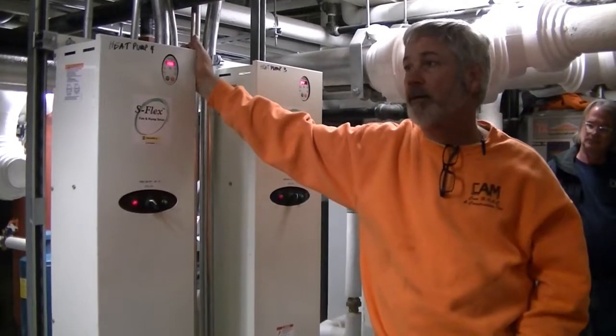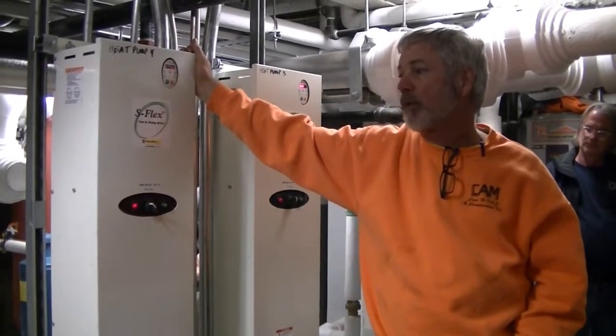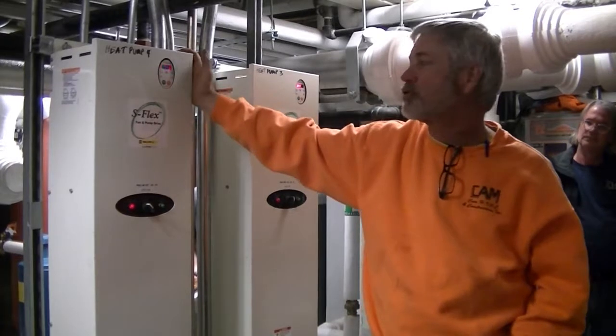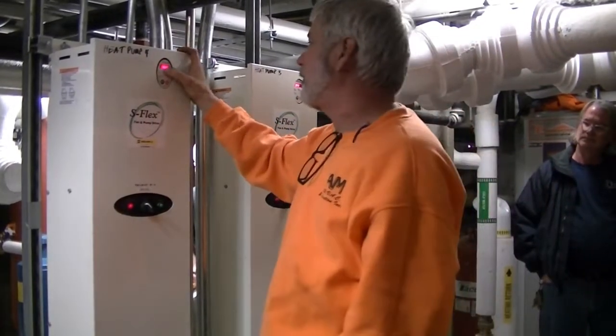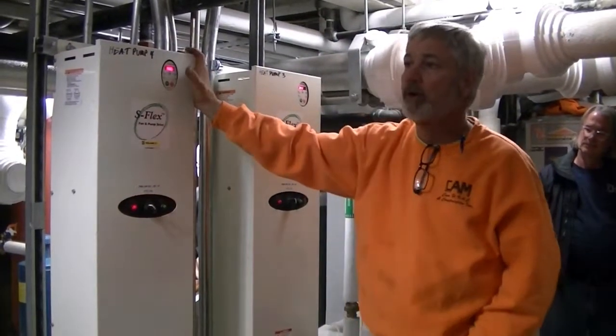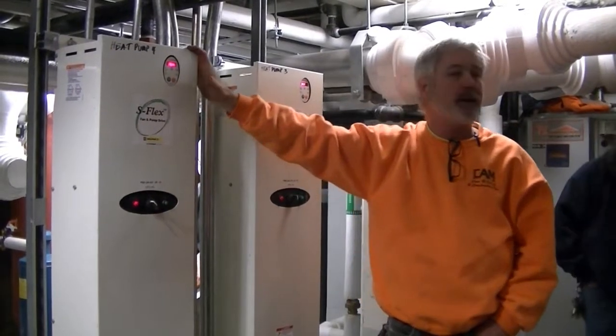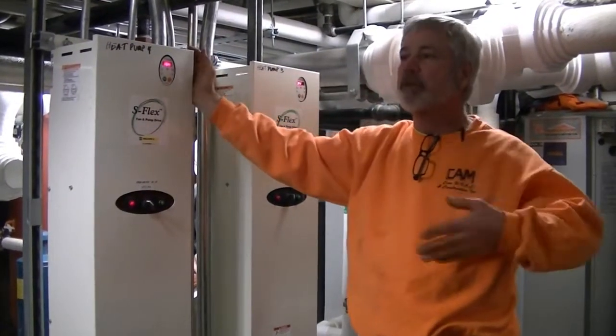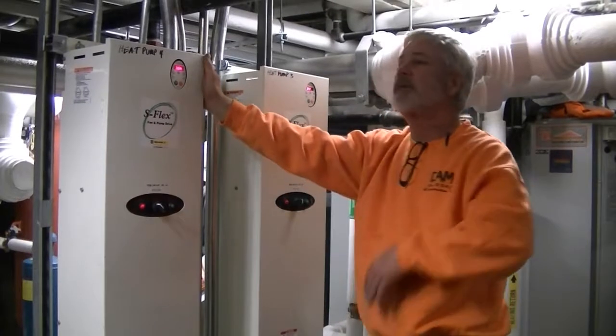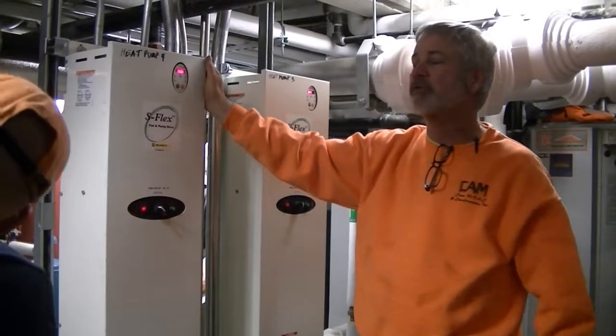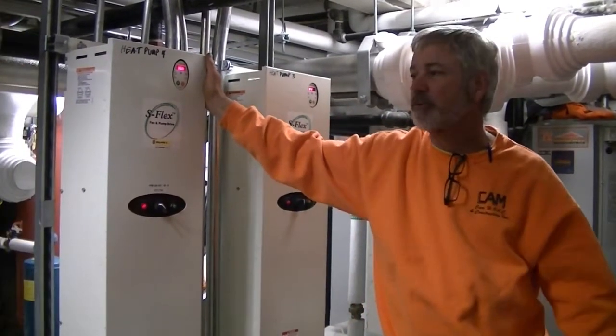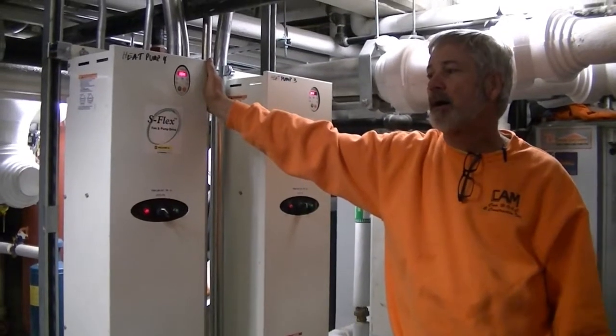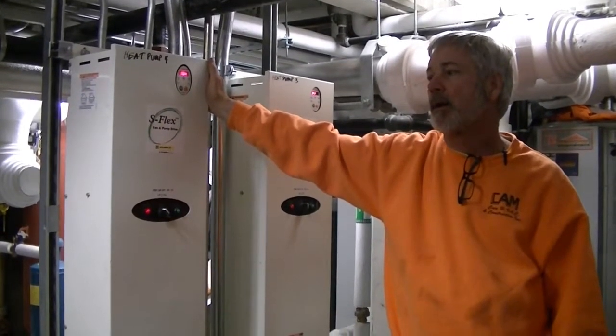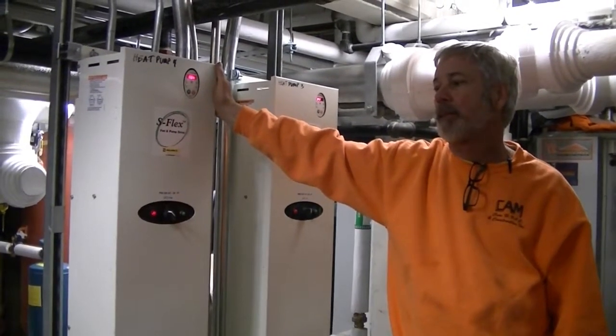So what should we do right away if that happens? Look at the DP, see what the drive's doing. Just make sure the drive is under its own control and nobody's bypassed anything. Just the obvious first, then you would investigate the piping system. See if perhaps there's a plugged strainer. And we're not shutting anything down, we're just watching it and letting somebody know there's something going on.